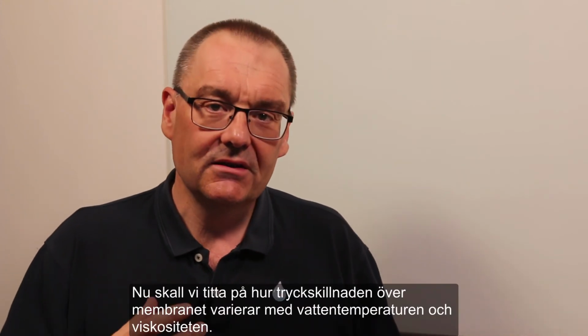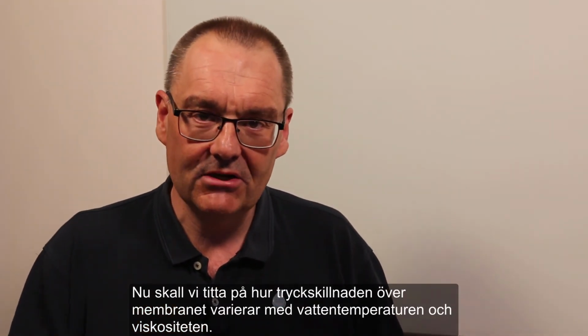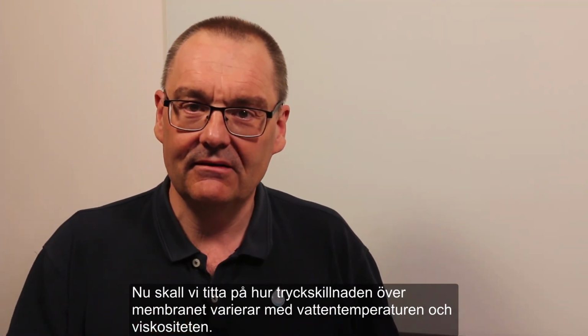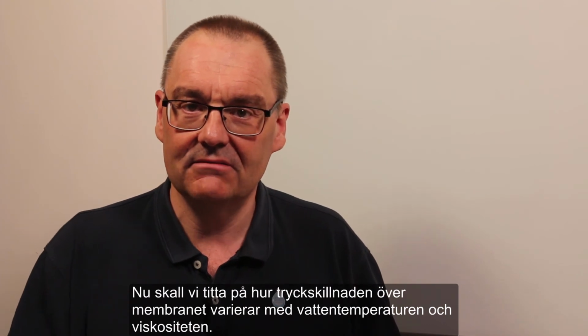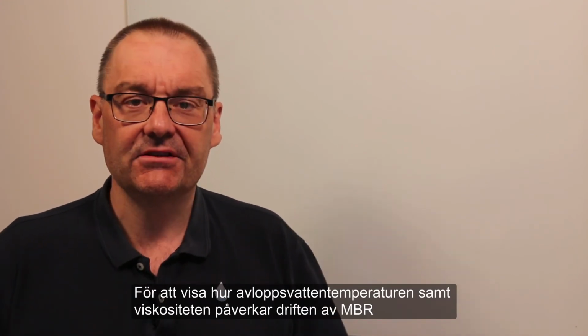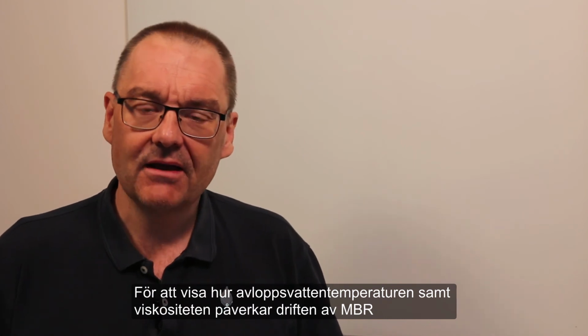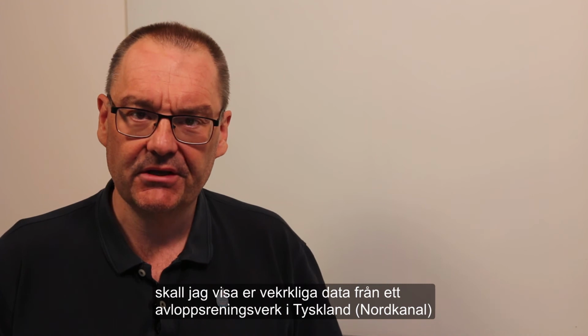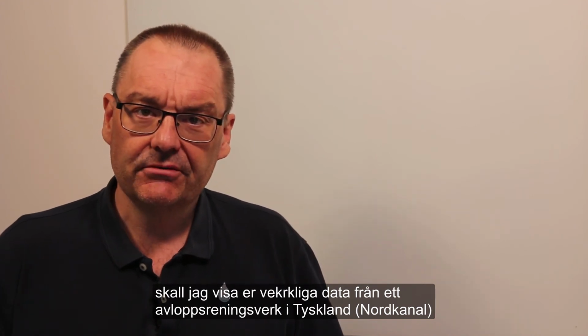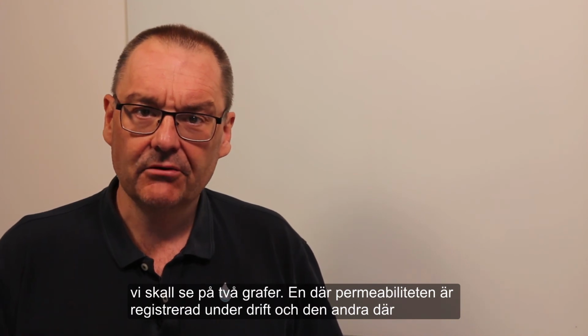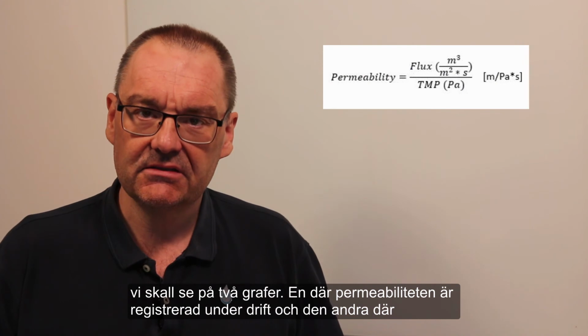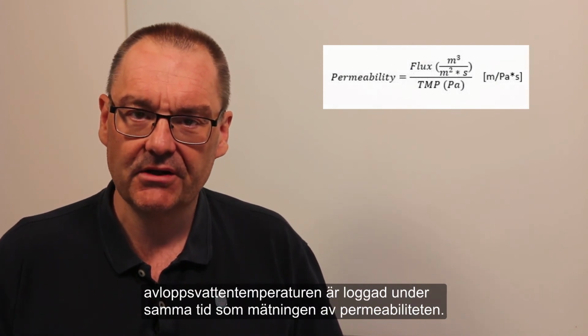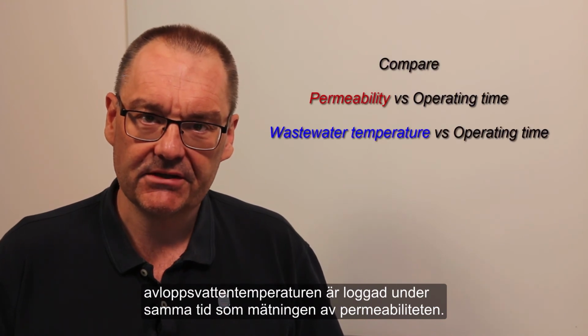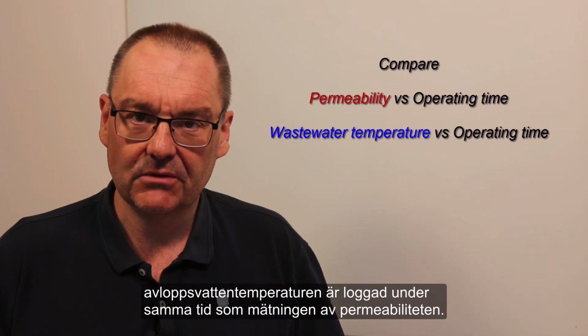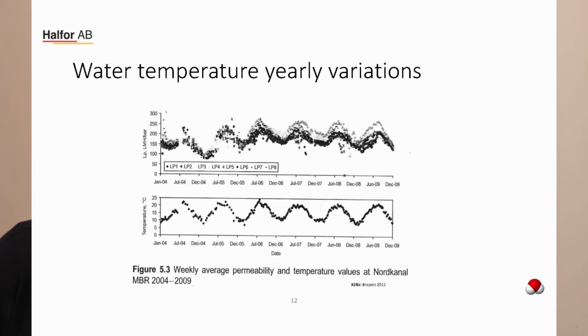So now we are going to look at the transmembrane pressure, which is directly correlated to the water temperature and the variations in viscosity. To show you how the water temperature and the viscosity affects the operation of the MBR, we're now going to look at some real figures from a plant in Germany called Nordkanal. And I will show you two graphs where we have measured in the one graph the permeability, which is the flux divided by the operating pressure, the transmembrane pressure, and a second graph with the temperature variations over the period when the permeability was measured, of course. So let's have a look at the two graphs right now.